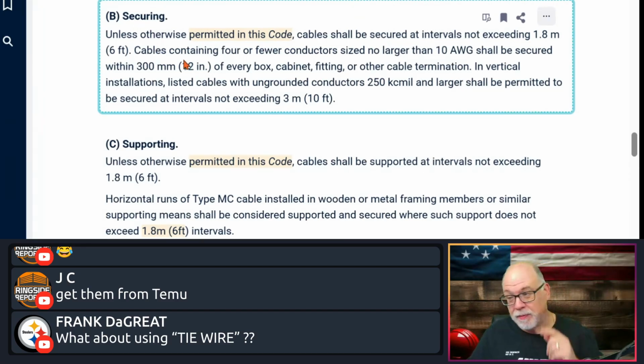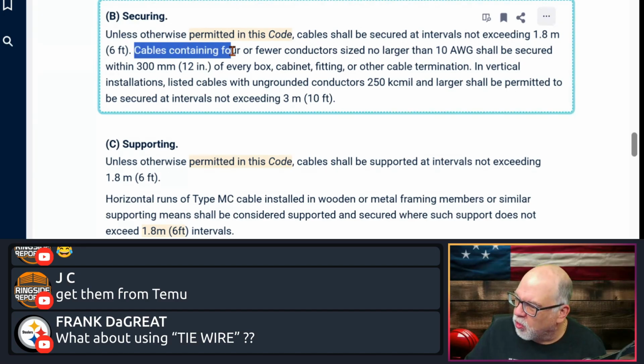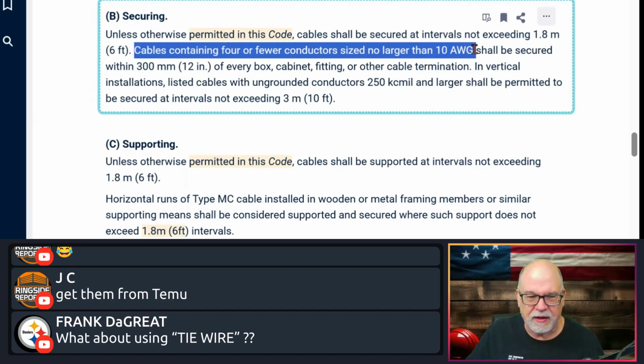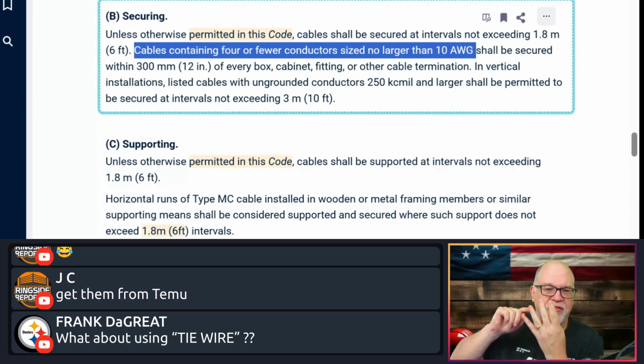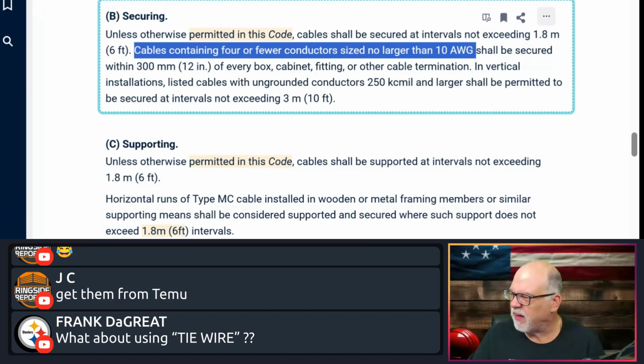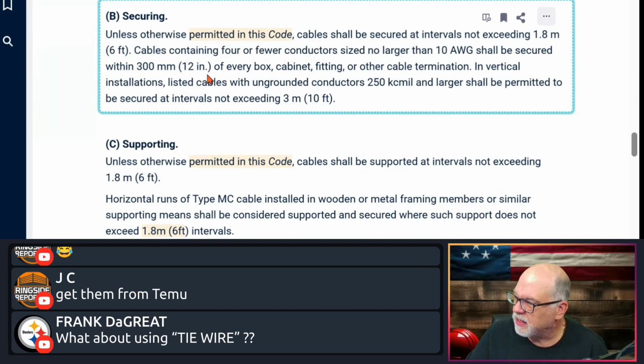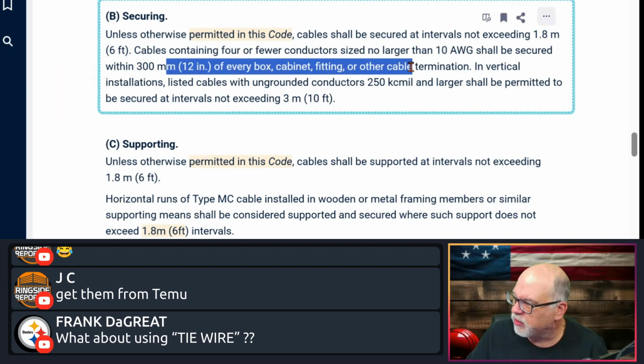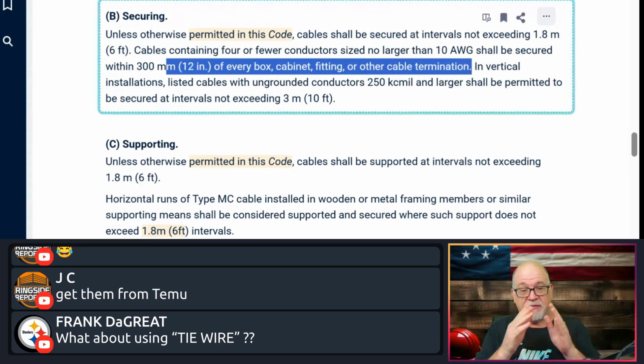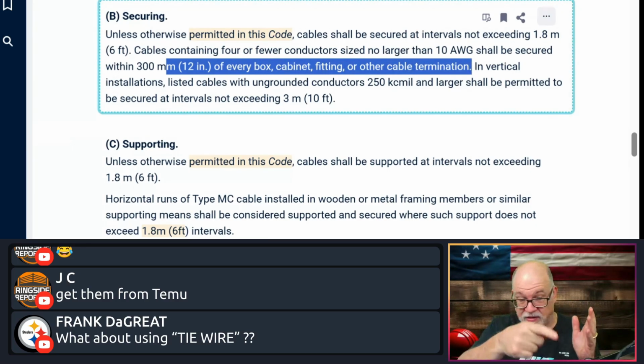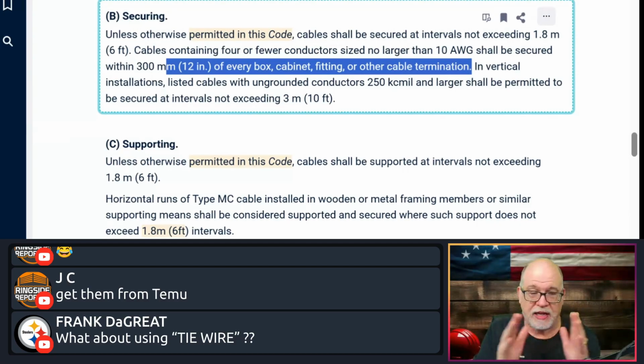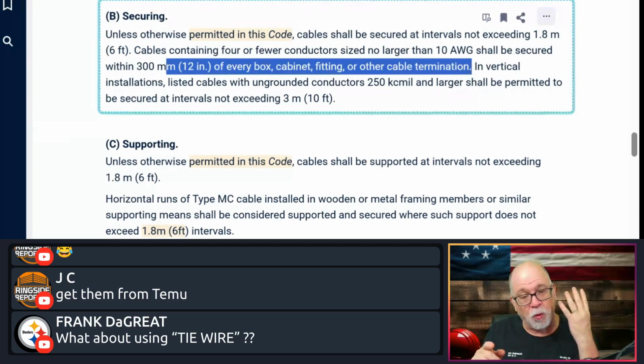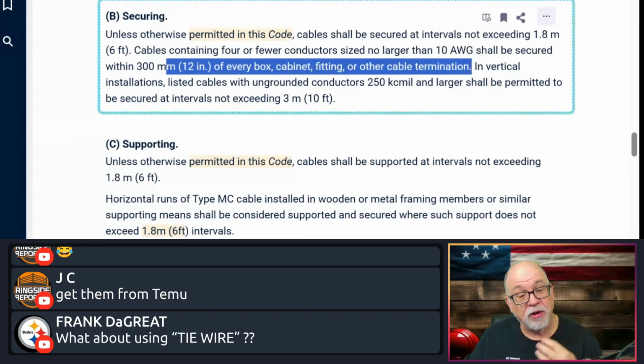However, here's something that people miss. It says cables containing 4 or fewer conductors, size no larger than 10. So it contains a maximum of 4, and the conductors inside of that MC are what? No larger than 10. So they're 10 and smaller. It says if that's the case, then it shall be secured within 12 inches of every box, cabinet, fitting, or other cable termination. So when you leave a box, you need to have a strap, a staple, a cable tie, or tie wire like Frank likes, within 12 inches. Anywhere in there, within 12 inches. Right? If it has 4 conductors or less, and they're 10 gauge and smaller. So it's to secure within 12 inches.